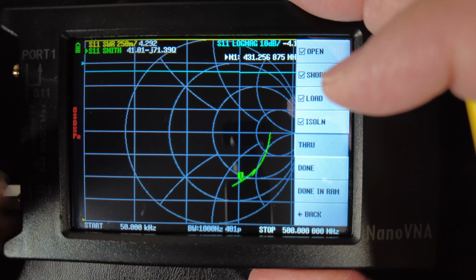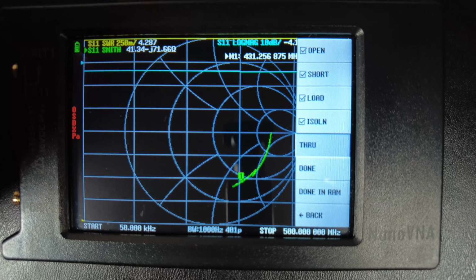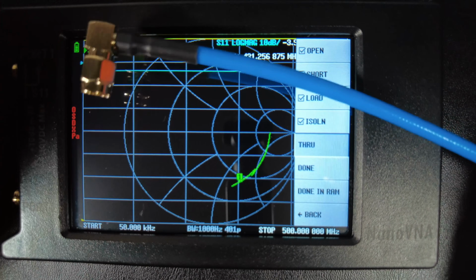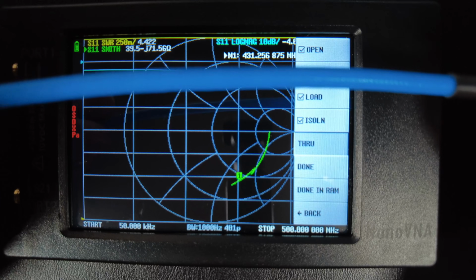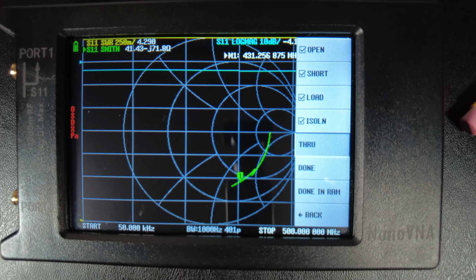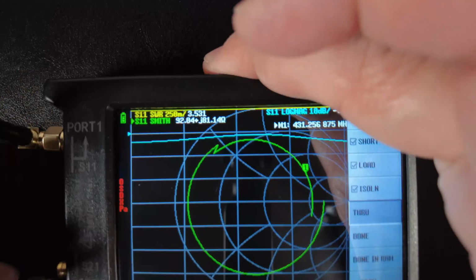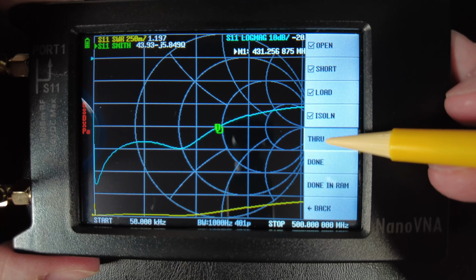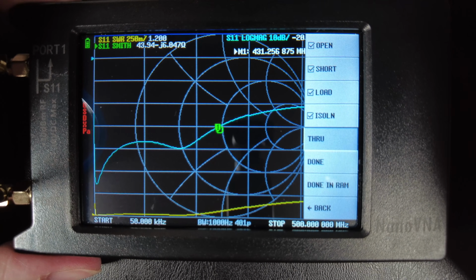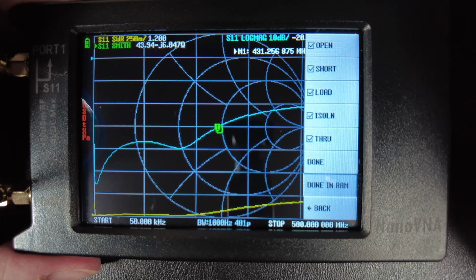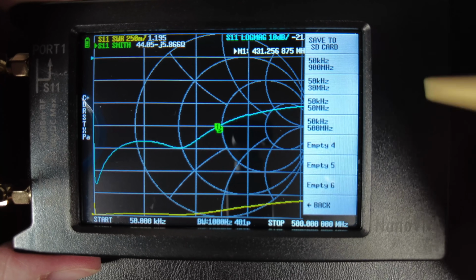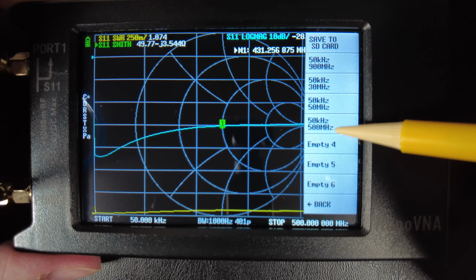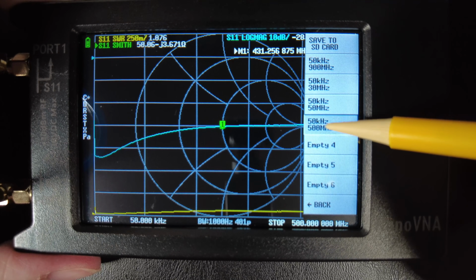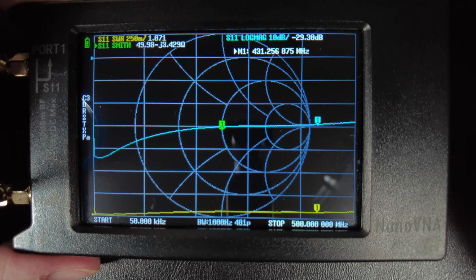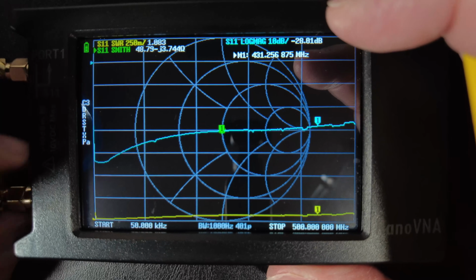Okay, and now we have to do the through calibration. Now for the through, I have a short piece of RG 405, that's low loss, and I'm going to screw that on. Okay, now I'm going to hit through. Now I'm going to hit done and save that to this memory slot here. I'm going to overwrite this 50 kilohertz to 500 megahertz. Okay. Now we'll disconnect that through.